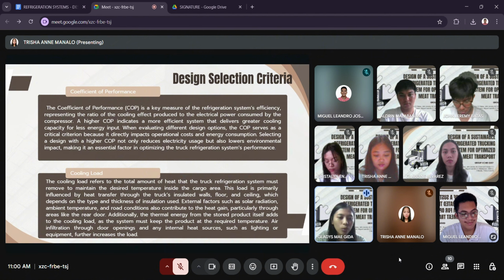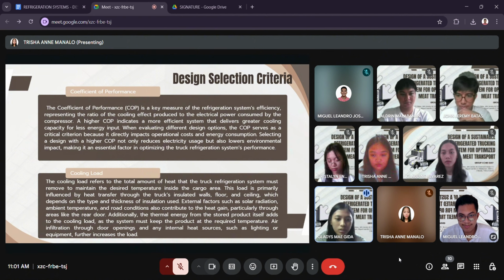Lastly is the cooling load. The cooling load refers to the total amount of heat that the truck refrigeration system must remove to maintain the desired temperature inside the cargo area. This load is primarily influenced by heat transfer through the truck's insulated walls, floor, and ceiling, which depends on the type and thickness of insulation used. External factors such as solar radiation, ambient temperature, and road conditions also contribute to the heat gain, particularly through areas like the rear door. Additionally, the thermal energy from the stored product itself adds to the cooling load, as the system must keep the product at the required temperature. Air infiltration through door openings and any internal heat sources, such as lighting or equipment, further increases the load.